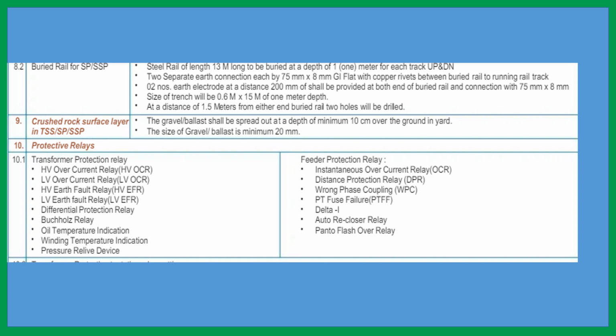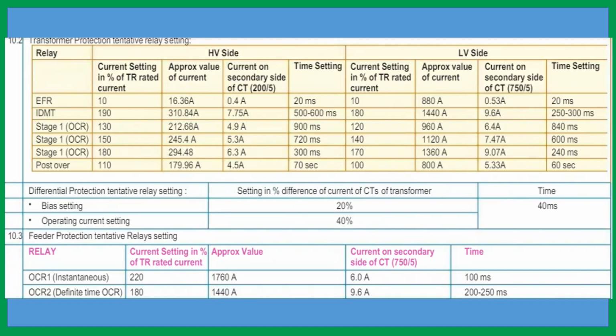Then pantograph flashover relay. Now it is used very little because it is used where, in front of the TSS, there is an insulated overlap. Nowadays it is PTFE neutral section, but in our time we were using insulated overlap. So these are the relays in the traction substation. Here the relay setting values they have given, but they will vary because our MVA is also varying, so they will also vary.